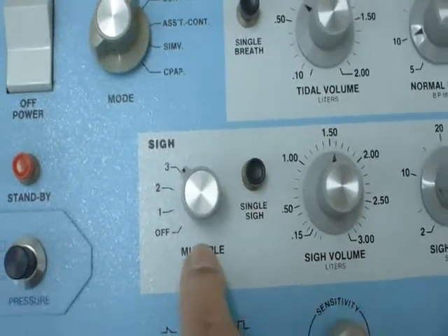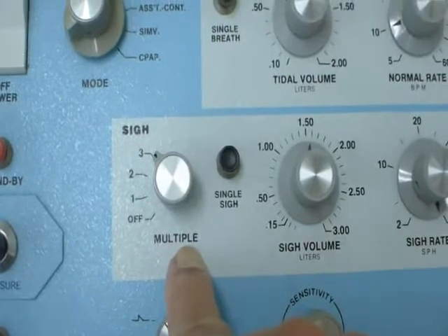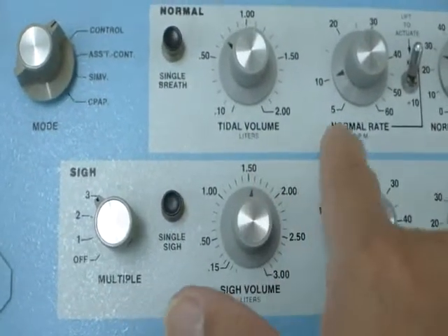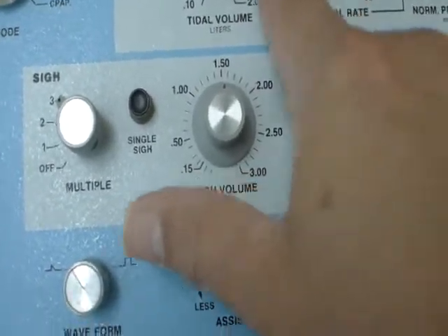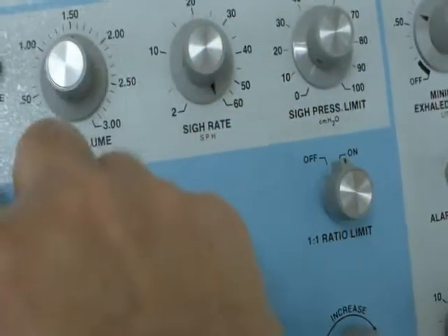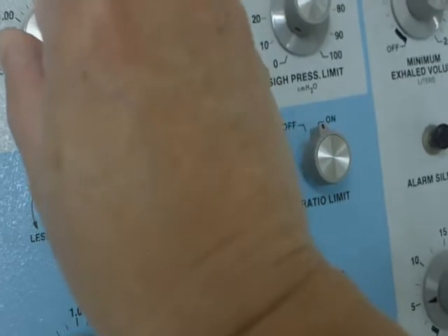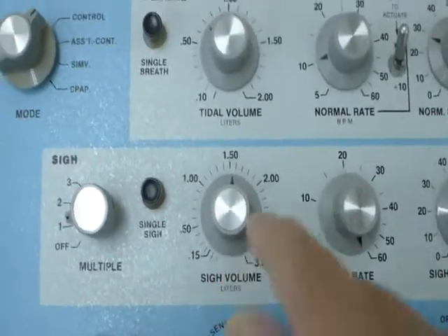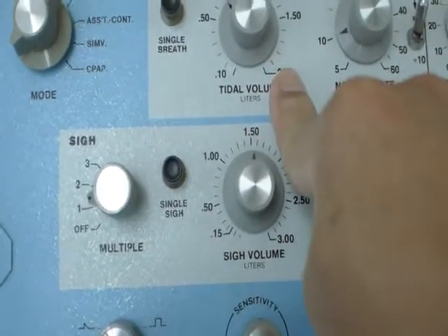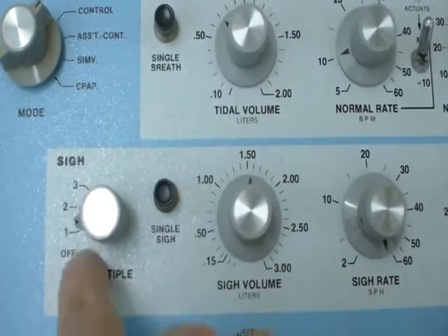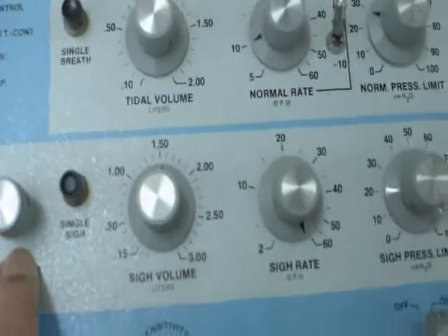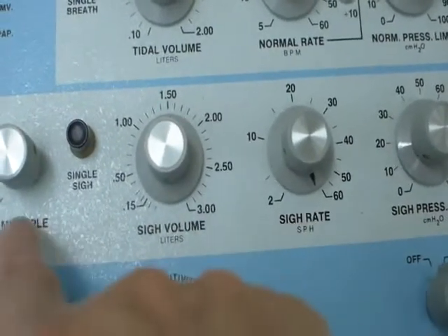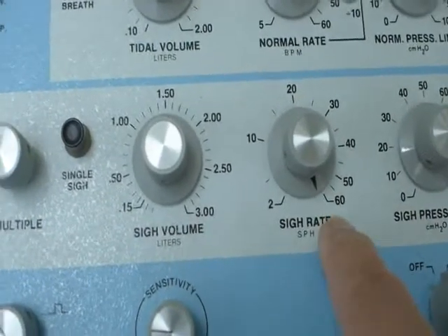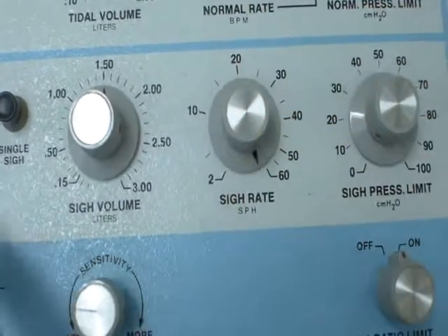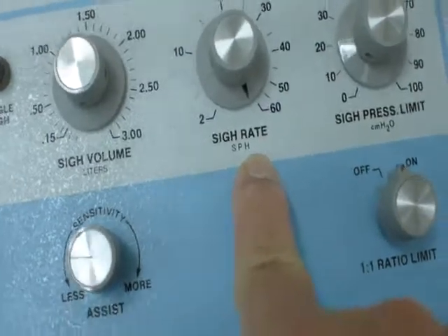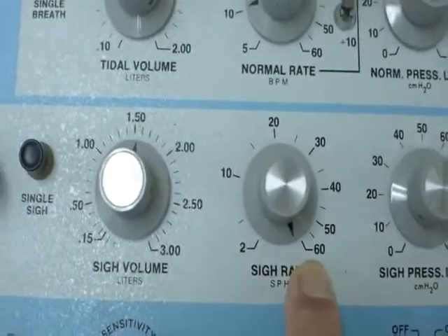All right, and then we have the sigh here. This is for a deep breath, so we can set this one. This is in addition to the normal respiration rate. So if you set, like, a 10, then you put the sigh at 1 and 1 here, and you can set the sigh to always have volumes more than the normal tidal volume. It has to be more than the normal tidal volume. And then we can set this here at 1. What does that 1 mean? It is a multiple of 60 over here. If it says 60 multiplied by 1, that means 60 deep breaths.